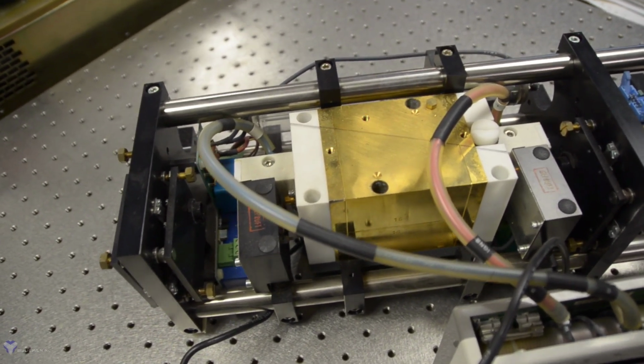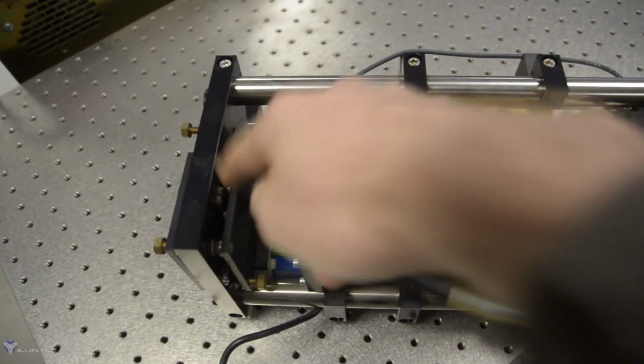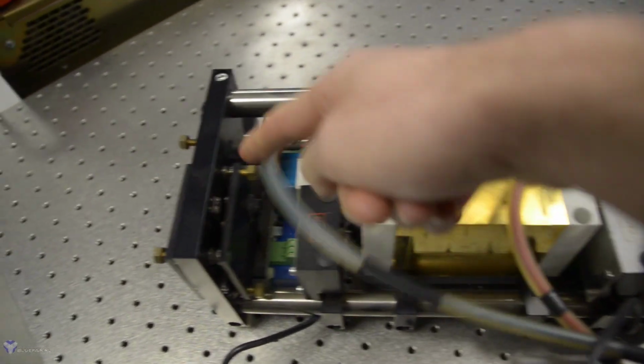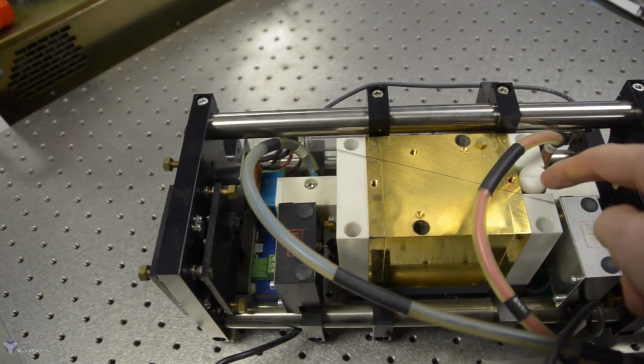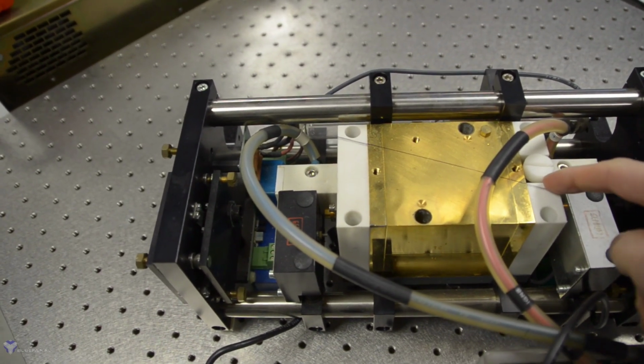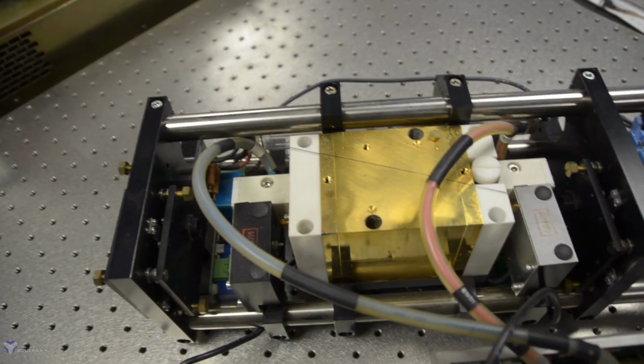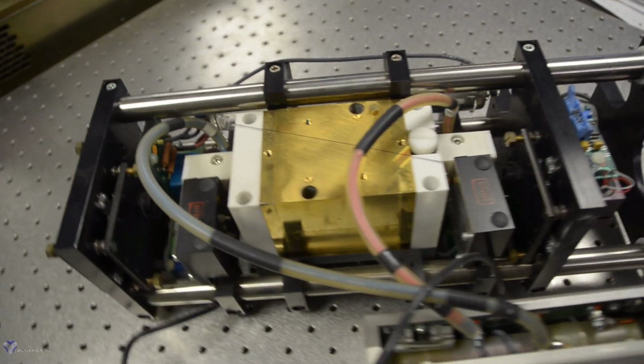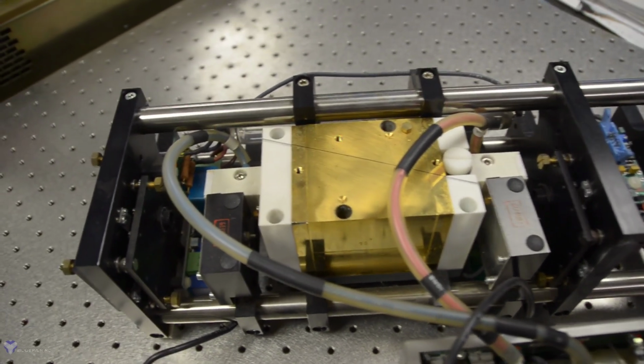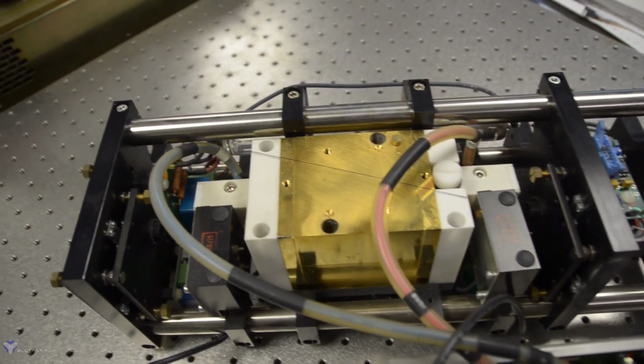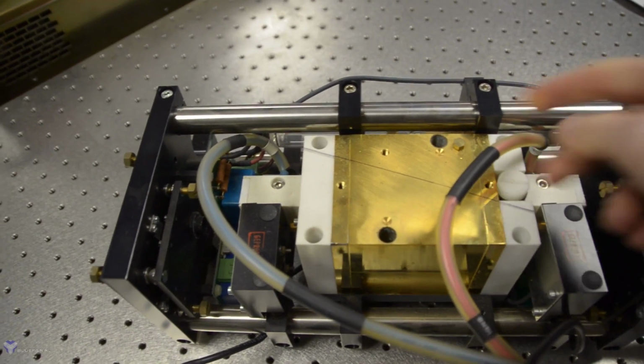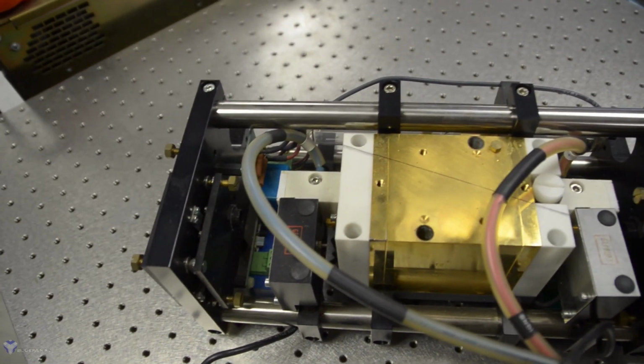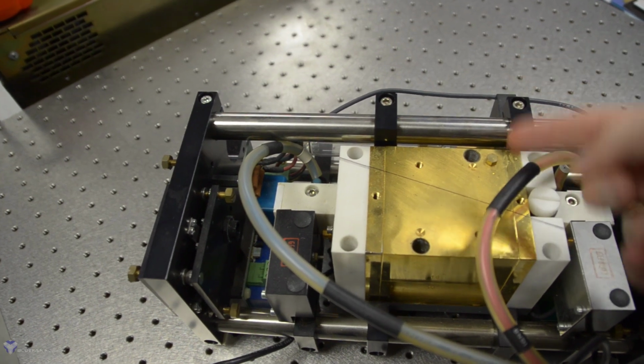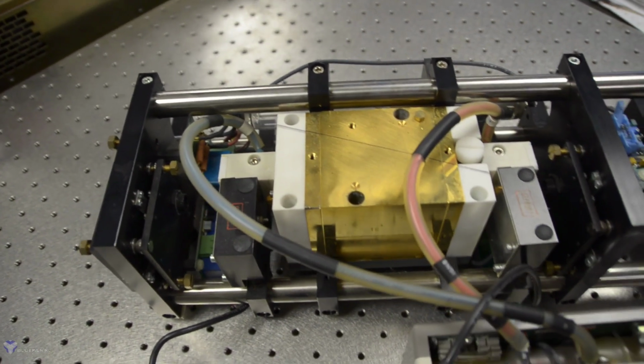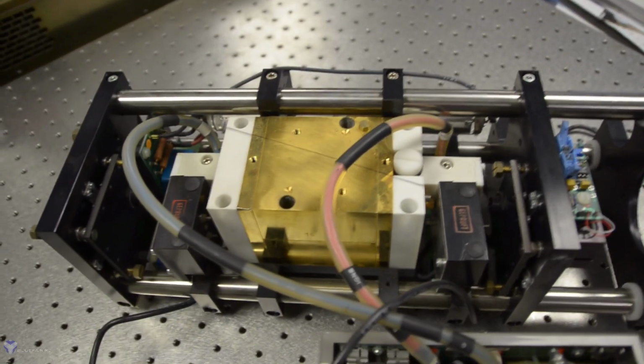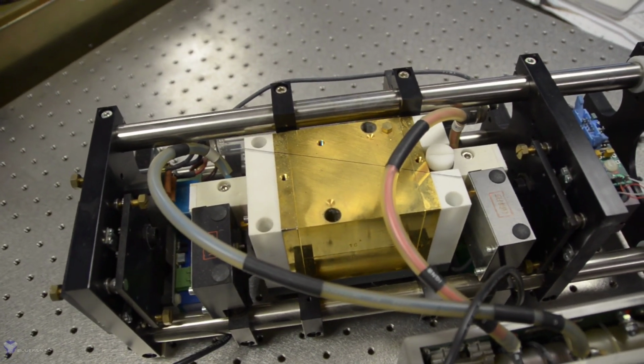Now the laser cavity is between these two mirrors, the output coupler and the high reflecting mirror, and in between here sits this big block, and inside here you have the neodymium YAG rod. That's the doped rod that is actually the laser crystal. Around it is a big reflecting cavity, so that the output of the arc lamp, you see the electrical connections of the arc lamp, that light is all reflected by this cavity to the laser crystal. It's probably an elliptical cavity, such that the light is properly coupled into the crystal.